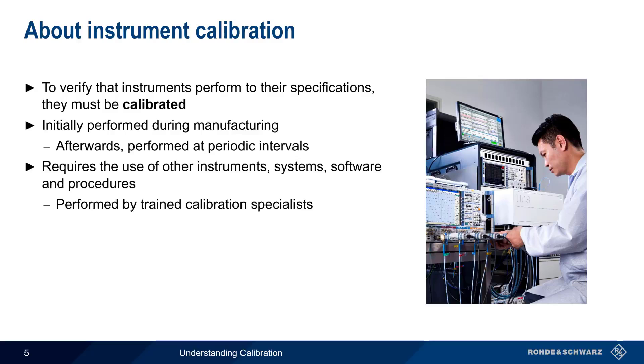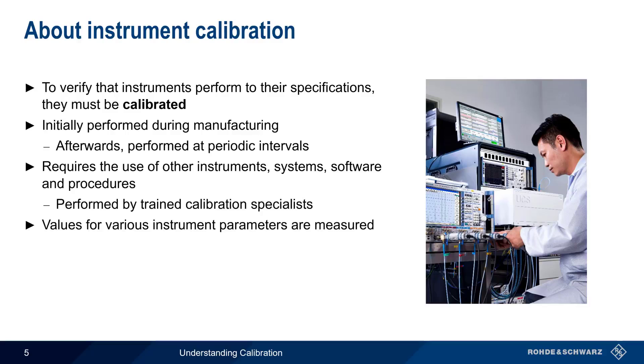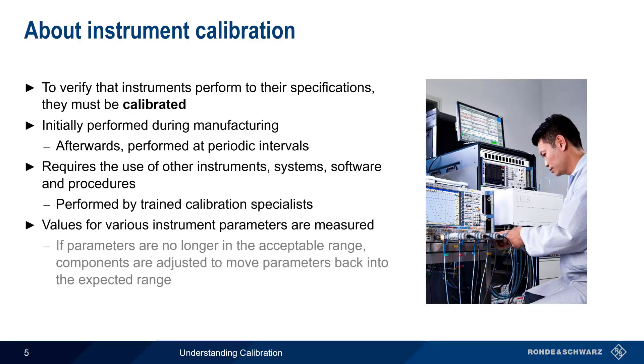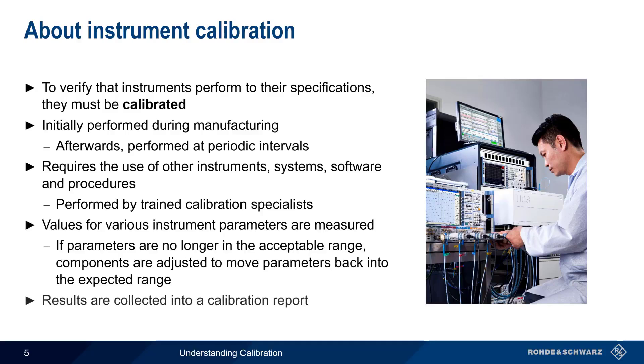During calibration, values for various instrument parameters are measured, and if these parameters fall outside of the acceptable range, they're adjusted back into this range. Upon completion of the calibration process, the results and other relevant data are normally collected into a calibration report.